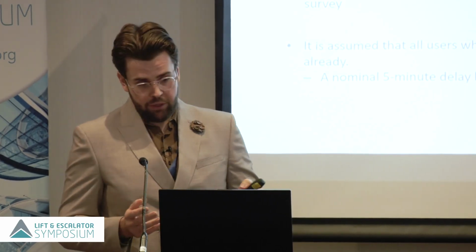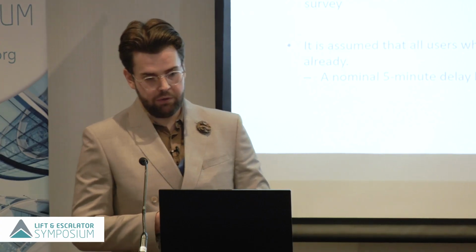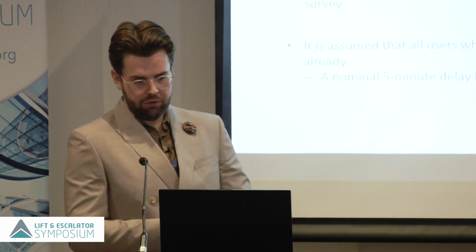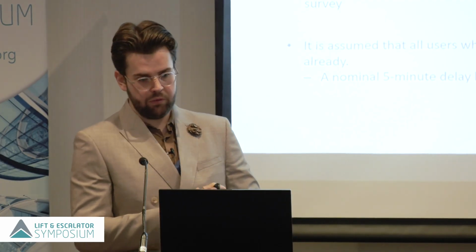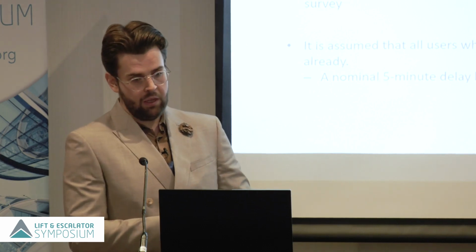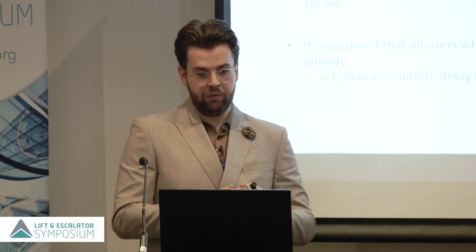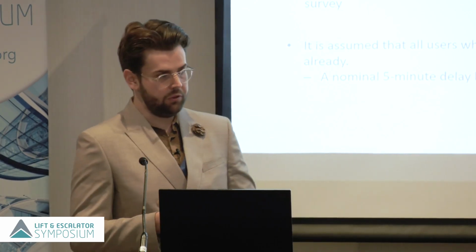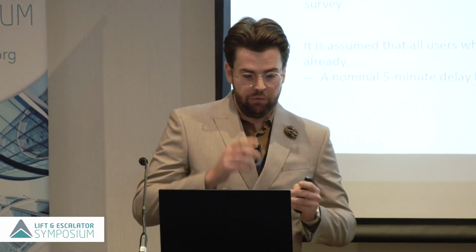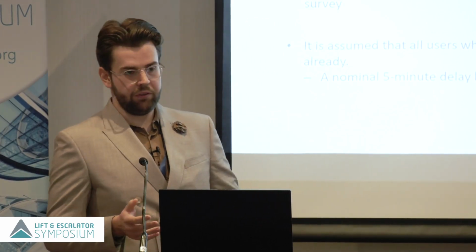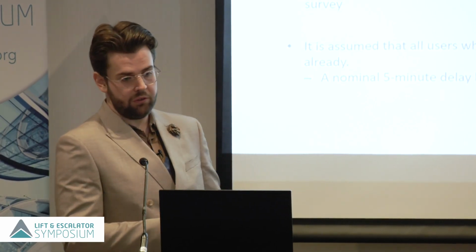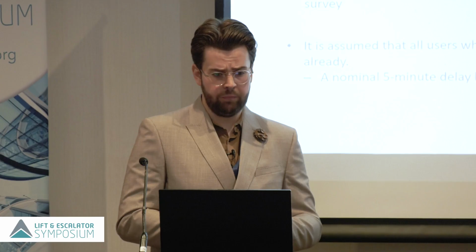So the quantity of people we've assessed has been provided by the fire engineer, and that's broken down into 3 main groups. It's important to note that the fire engineer has written their fire strategy at 1 person per 6 metres squared, and we have analysed the building for our general lift traffic purposes at an effective density of 1 per 12.5. The figures have been broken down into these groups, and the figures have come from the latest Department for Work and Pensions Family Resources Survey for the South East and London area.